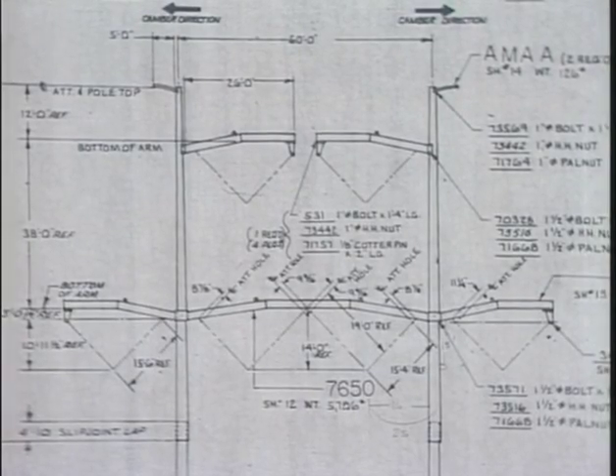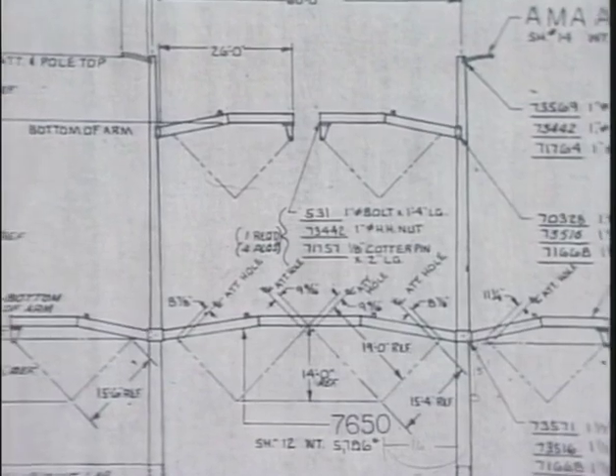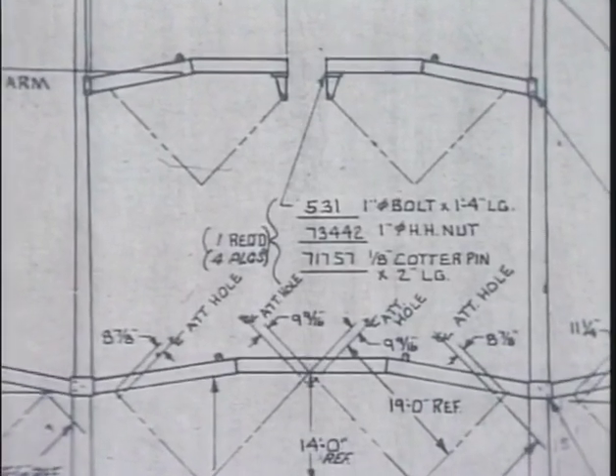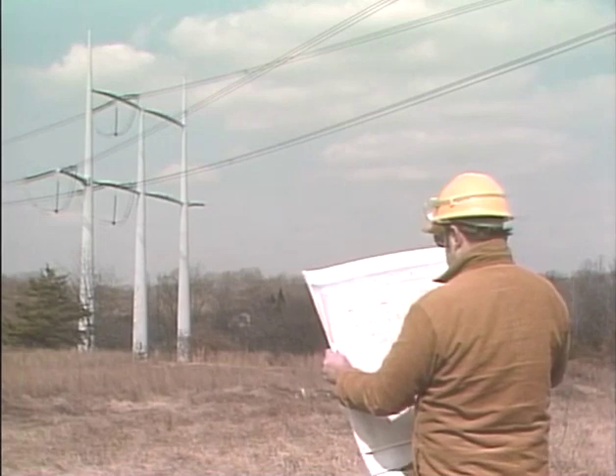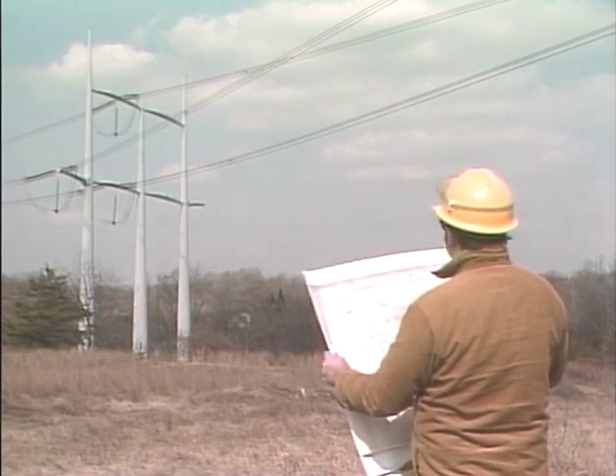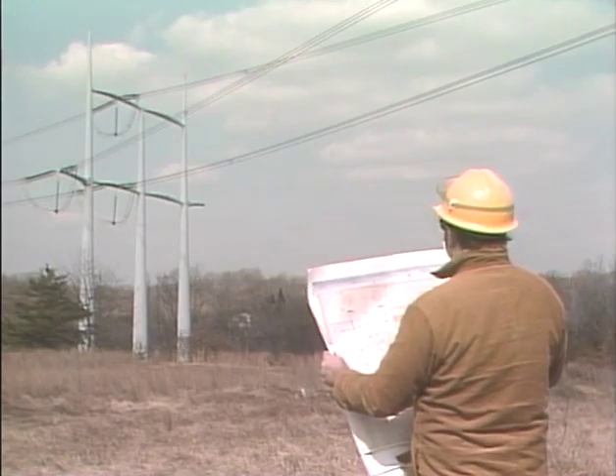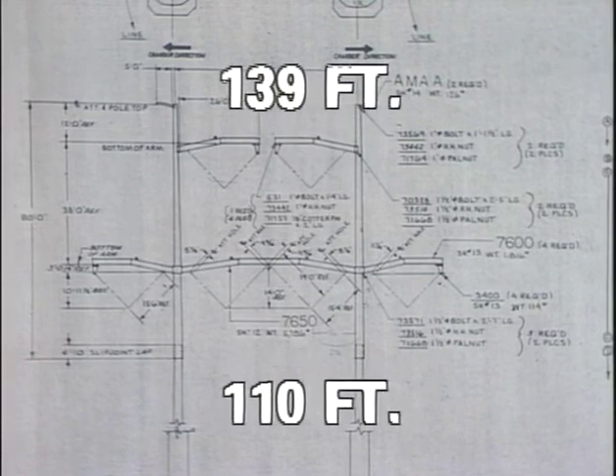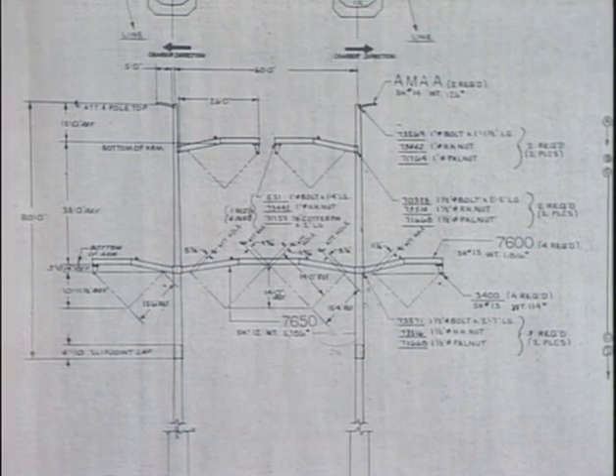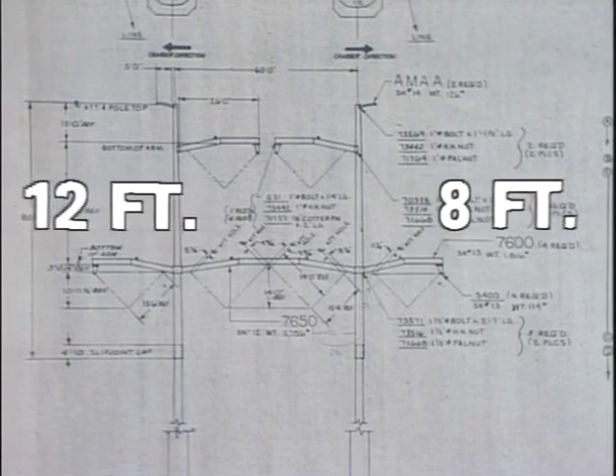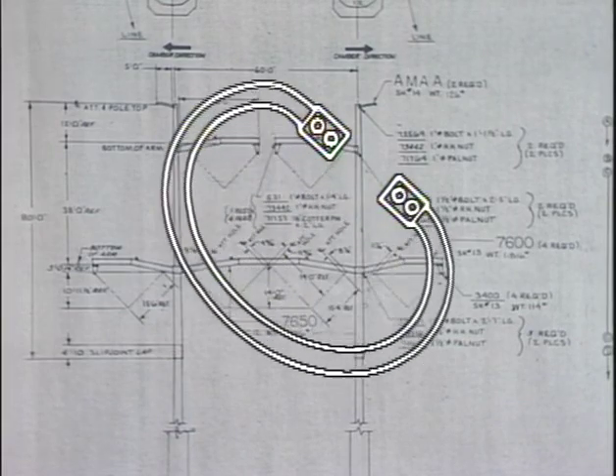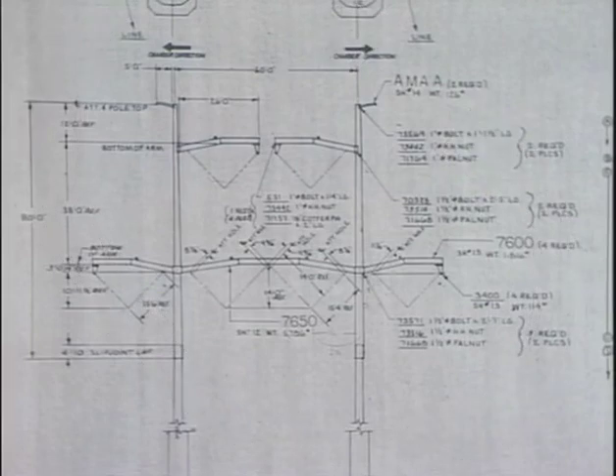The blueprints for a high-voltage AC transmission system may appear to be just numbers and symbols on a piece of paper, but the linemen who actually put the system together must follow these plans exactly. Conductor sizes and materials, structure heights, line spacing, and devices such as spacers and corona rings that are added to transmission lines are all included in the plans of a transmission system for specific reasons.